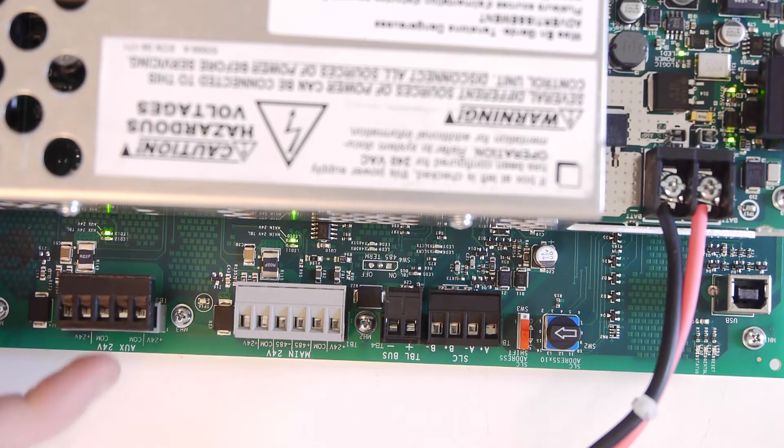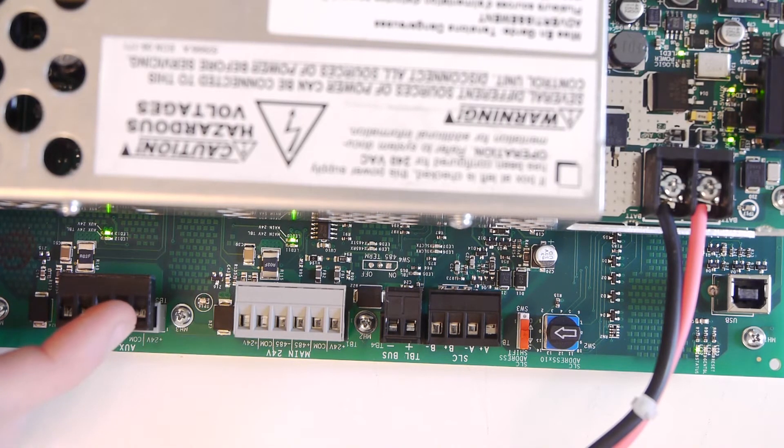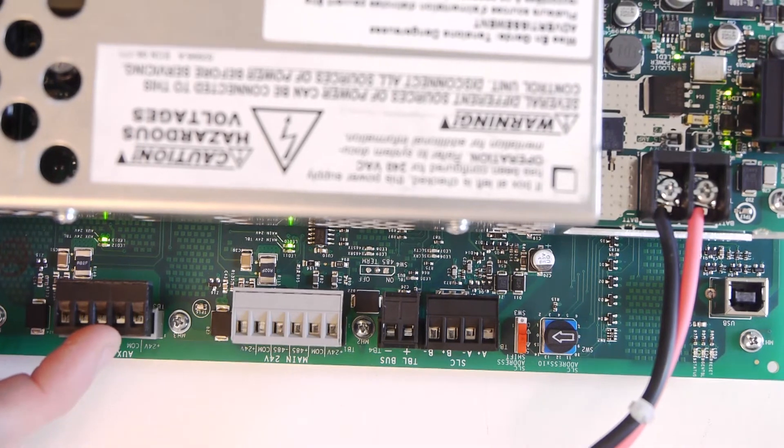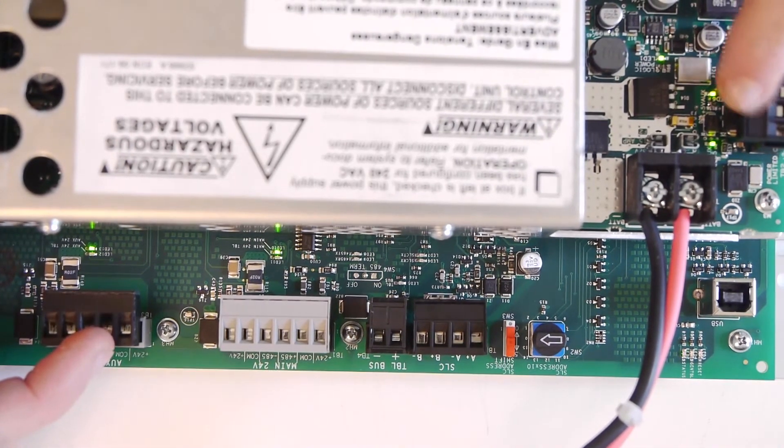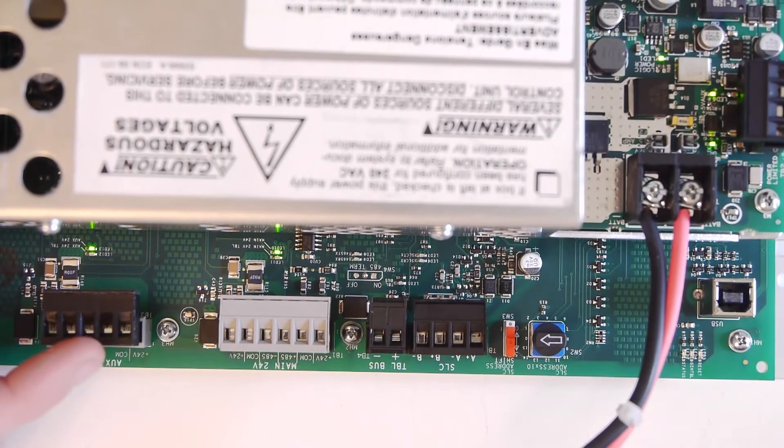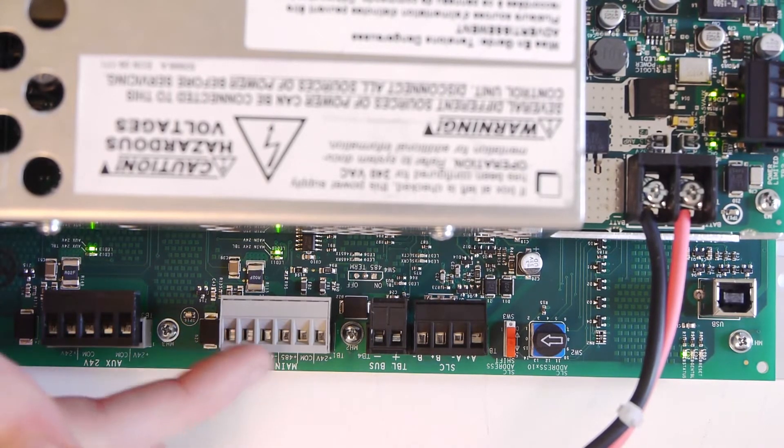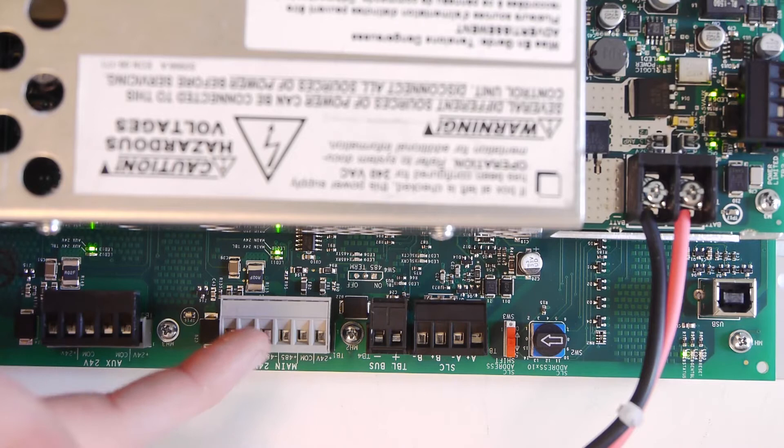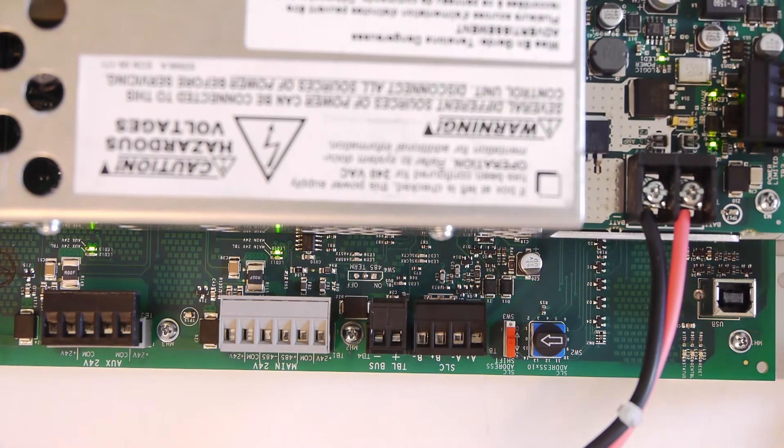And the last set of terminals on this thing are the auxiliary 24-volt output. So this is what you would use just to power anything on your system. So this shares the power between this terminal right here and this, and you can pull three amps between these two. These two rails are actually on their own, and you can pull five amps from this. So that's a basic overview of all the terminals.